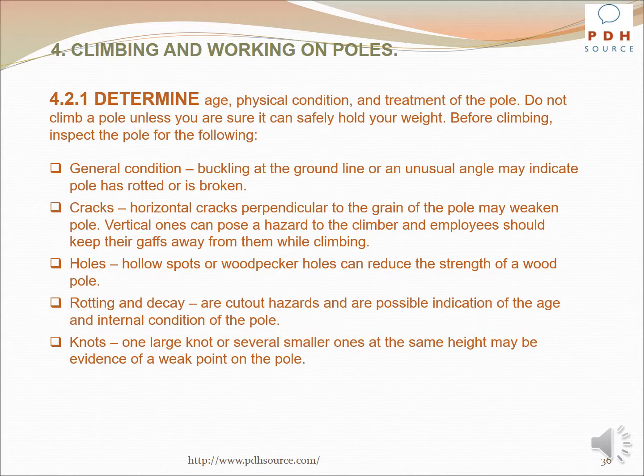Vertical ones can pose a hazard to the climber, and employees should keep their gaffs away from them while climbing. Holes: hollow spots or woodpecker holes can reduce the strength of a wood pole. Rotting and decay are cutout hazards and are possible indication of the age and internal condition of the pole. Knots: one large knot or several smaller ones at the same height may be evidence of a weak point on the pole.